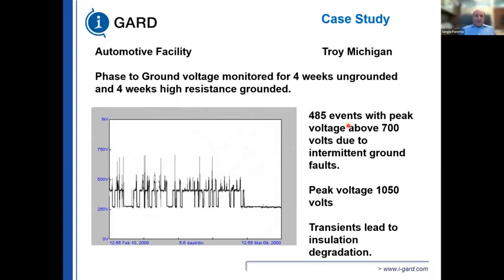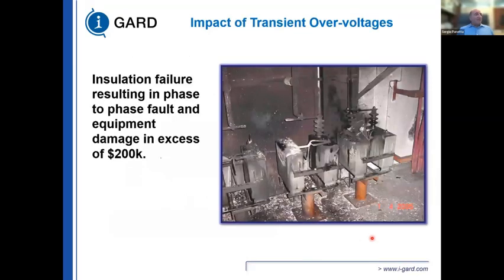So there's a case study in Michigan where they looked at an ungrounded system, and they noted that they had 485 events of peak voltages above 700 volts due to intermittent ground faults. And the peak voltage was at 1,050 volts. And this transient led to insulation damage. Same thing in a medium voltage type of system. These are surge capacitors, and they fail due to the overvoltages caused by an ungrounded system.